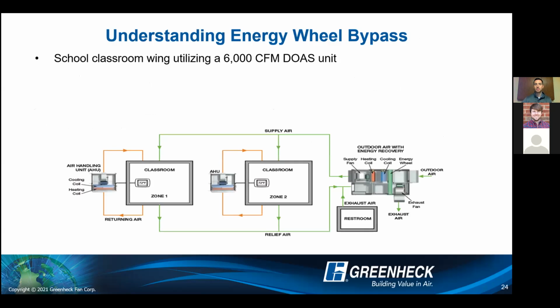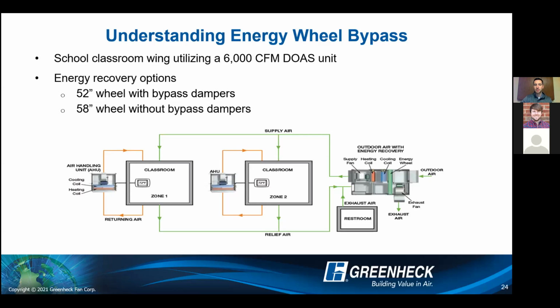The third option that you might be familiar with, maybe you prefer, or maybe you see in the market, is wheel bypass. We do get this request, we do see it, but I want to break that down a little bit and give you our stance on it and when you would see it on the RVE product lines. First, I want to give an example of a classroom that is 6,000 CFM. In that 6,000 CFM DOAS unit, you have two energy recovery options. You have a 52-inch wheel with bypass dampers for economizer, or you have a 58-inch wheel without bypass dampers. Obviously, without the bypass dampers, we have room to expand that energy recovery wheel.